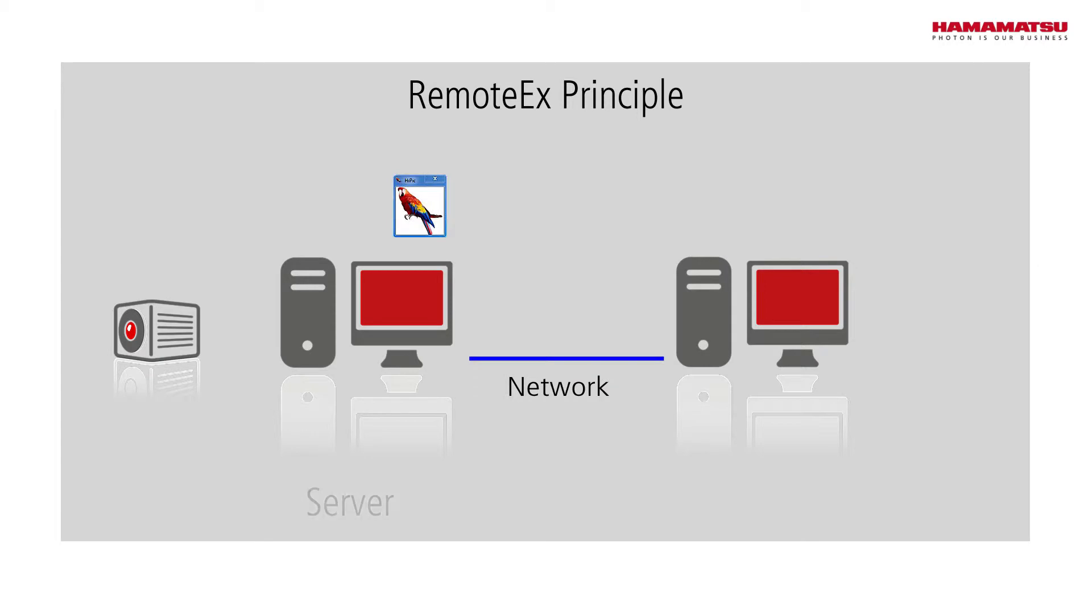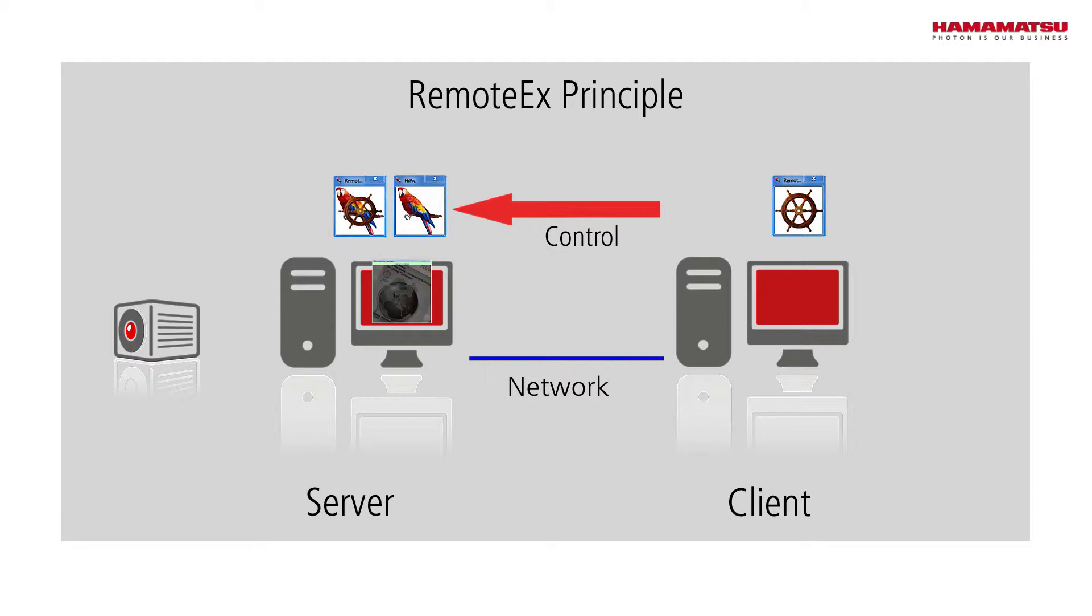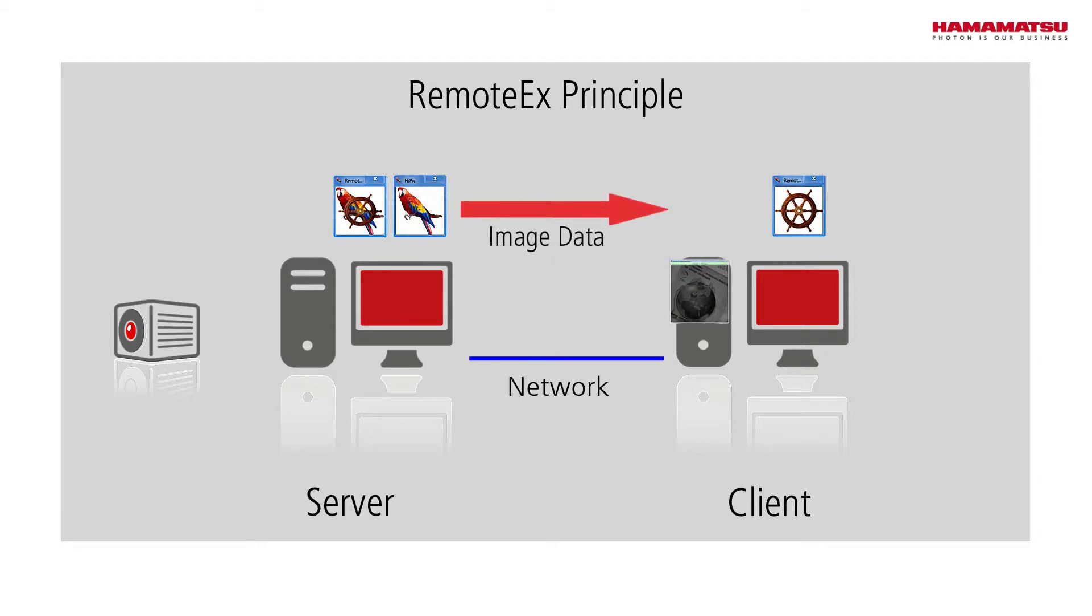RemoteEx is the server component in a client-server application and runs on the computer where the HiPIC is installed. The client component can run on any other computer that has a network connection to the server. In this configuration, the HiPIC can be controlled from the client computer and image data can be transferred to the client.